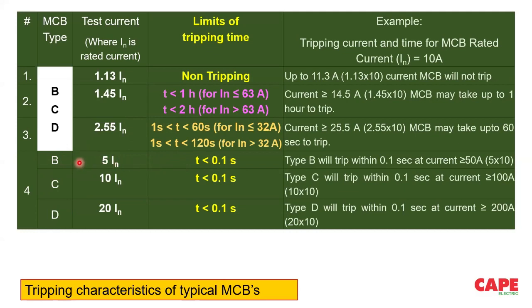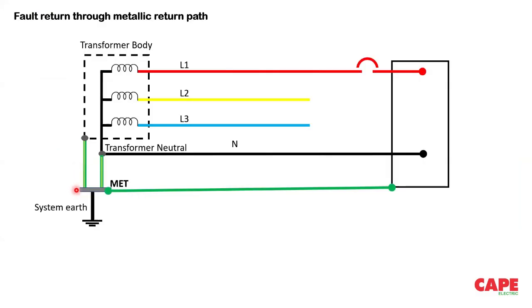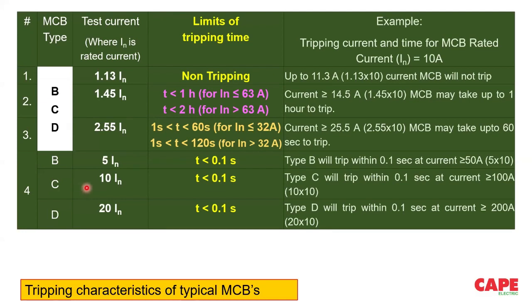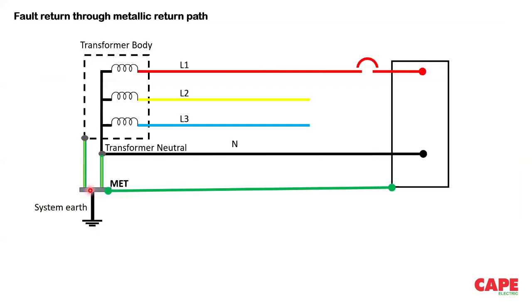Now, these type B MCBs are generally not available in the market. You cannot buy them across the counter. If you go to a shop and ask for a type B MCB, they will say, I need 1 week, or 2 weeks, for arranging the material, which is actually not good. As a result of non-availability of the material, we always use type C MCB. Please note that fault protection, shock protection by a type C MCB, is a little bit more difficult than with a type B MCB in a TN system.